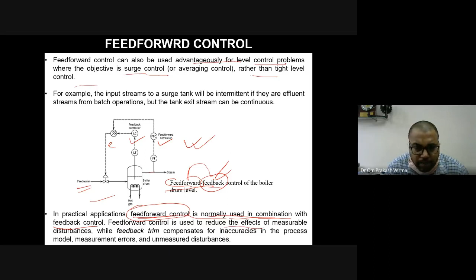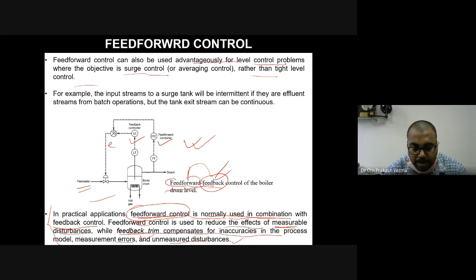Feed forward control is used to reduce the effect of the measurable disturbance, as already discussed. Whatever the measurable disturbance is, that will be reduced with the help of the feed forward control, right? While the feedback control compensates the inaccuracy in the process model, measurement errors and unmeasured disturbance, it will be very, very important. Whatever the drawback of the feed forward controller is compensated by the feedback, and the drawback of the feedback controller is compensated by the feed forward controller, right? Feed forward controller needs an accurate model. However, the feedback controller does not need the accurate model. So these both are compensating each other.